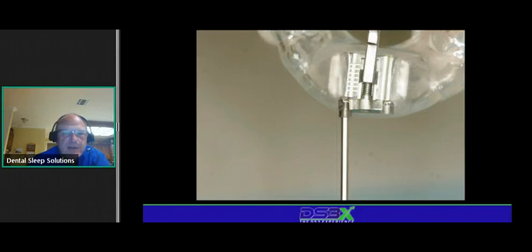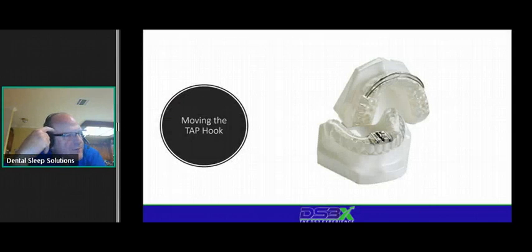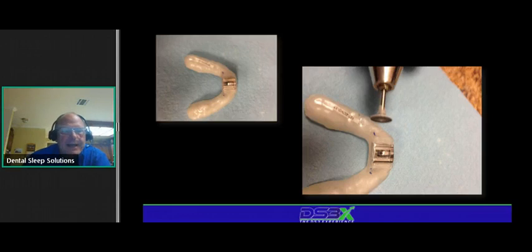Be aware: you can get the screw turned around — it goes in either side just as easily. The DreamTap and TAP 3 Elite are different because the plate on a DreamTap is on the bottom and on the old TAPs it's on top. Take a picture with your phone or have an old one next to you so you don't get confused. Put the plate back on, trim if needed, put the screws in, screw it down. You've now changed the range of motion by about 5–6 millimeters.